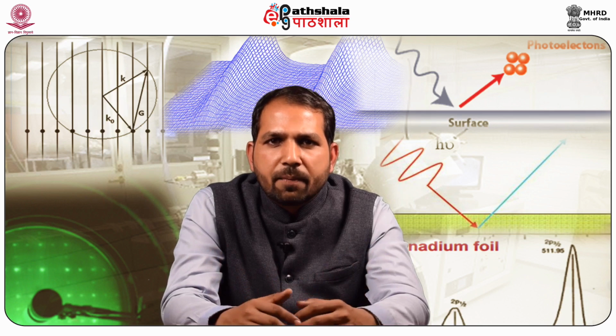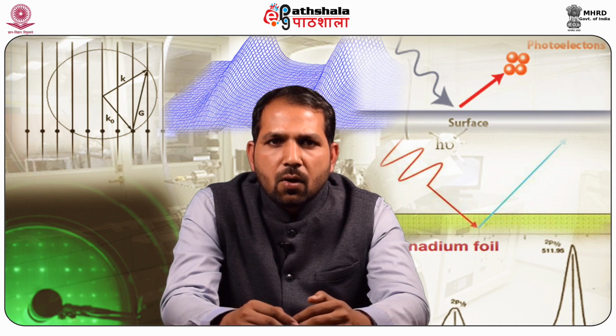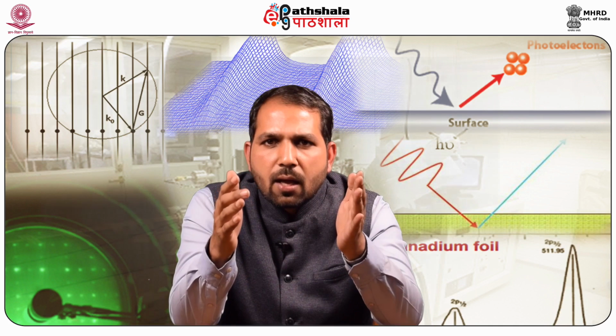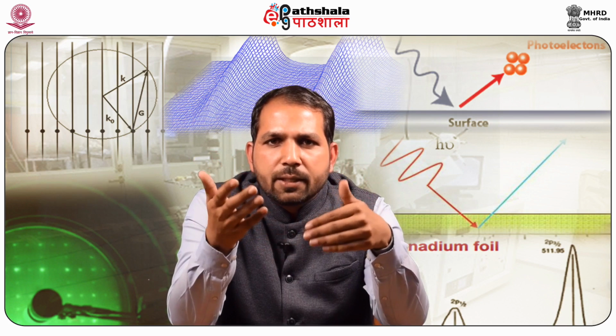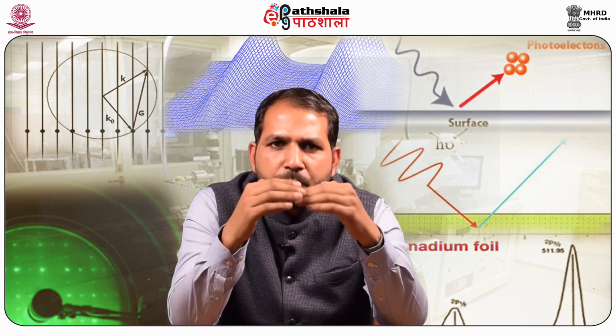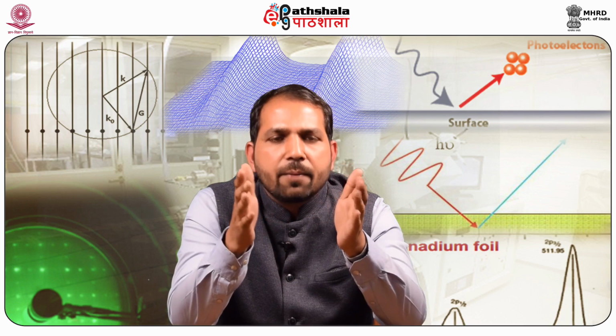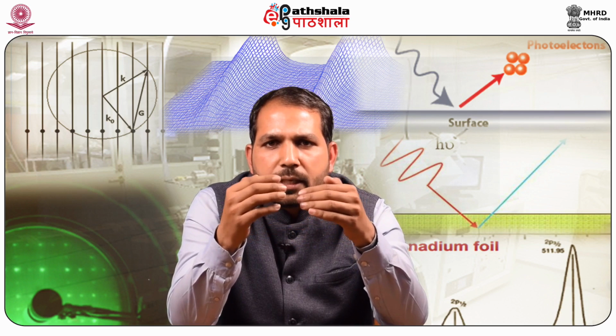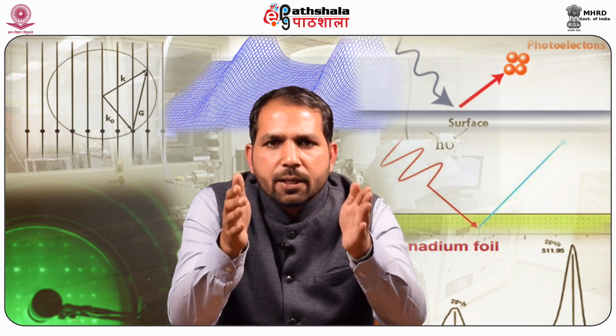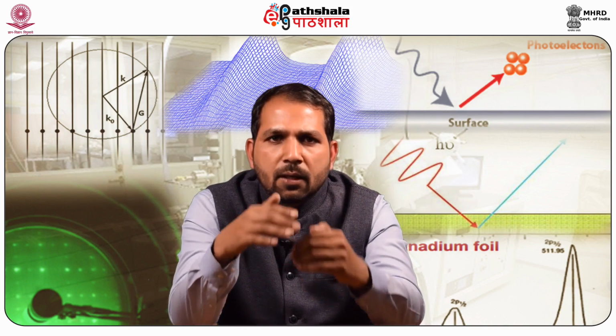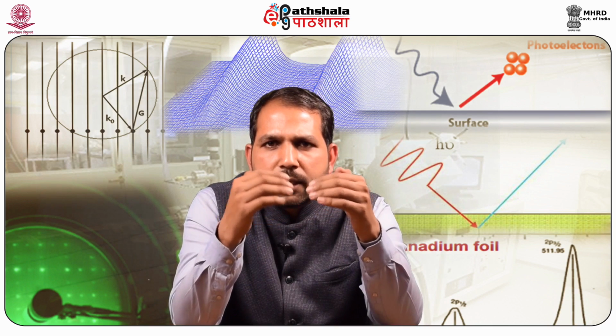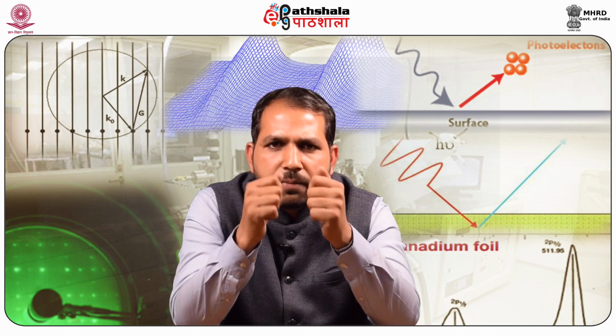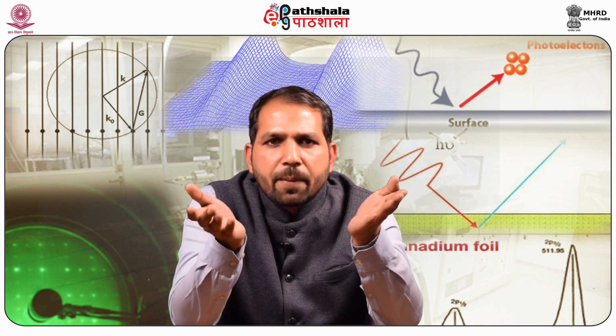Introduction. A low temperature magnetic force microscope was constructed for this thesis based on Dan Rogers' MRFM, magnetic resonance force microscope, design. As with all low temperature scanning microscopes, our MFM is a fairly complicated instrument. It incorporates a high vacuum probe, cryogenic vibration isolation, a fiber optic sensor, microfabricated cantilevers, and a variety of commercial and homemade electronics and control software. The functional completed instrument is a powerful tool for characterizing materials through high resolution magnetic imaging.